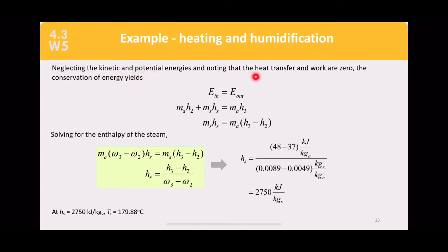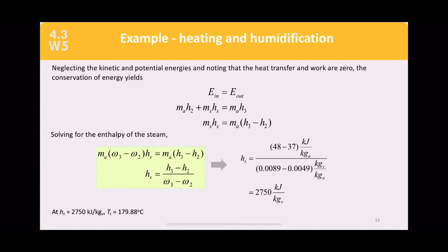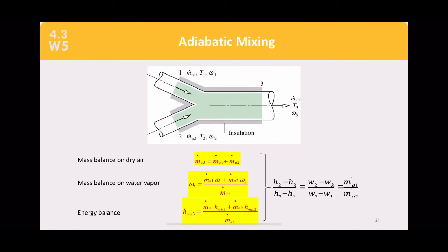Applying conservation of energy for the humidification section (no heat transfer, no work): m_a·h2 + m_s·h_s = m_a·h3. Solving for enthalpy of the steam: h_s = (h3 - h2) / (ω3 - ω2) = 2750 kJ/kg of water vapor. From steam tables at h_s = 2750 kJ/kg, the saturation temperature of the injected steam is T_sat = 179.88°C.